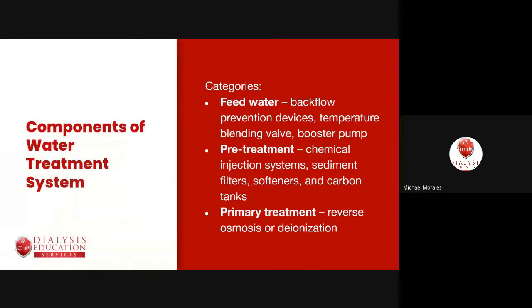We break water treatment down into three categories: feed water, pre-treatment, and primary treatment. Feed water deals with getting the water into our facility and running it through our system — ensuring it can't back-flow into the safe drinking supply, adjusting temperature, and using pumps to establish pressure.